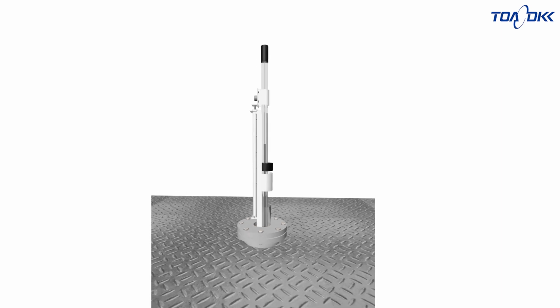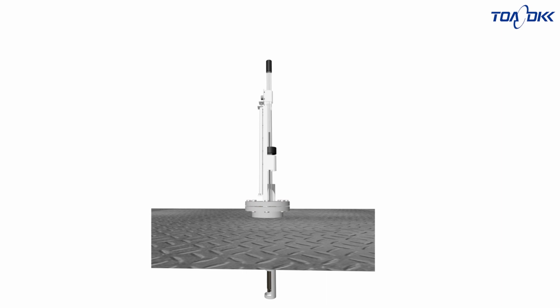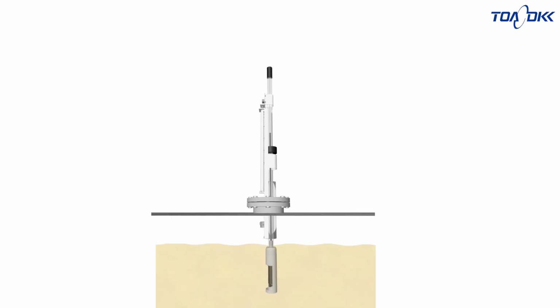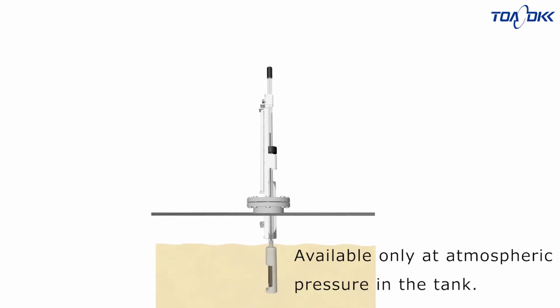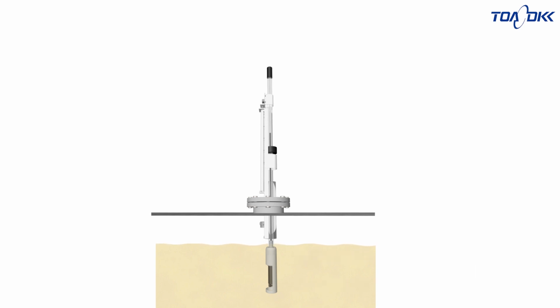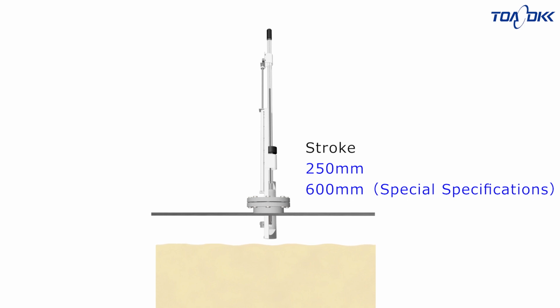Here is an image viewed from the side. It is not sealed with a flange, so it can only be used at atmospheric pressure, with no pressure applied in the tank. This is the state that we are measuring. During cleaning and calibration, the holder rises by the air cylinder. Stroke length is 250 mm in standard specifications. A stroke length of 600 mm, as shown in the illustration, is also available.